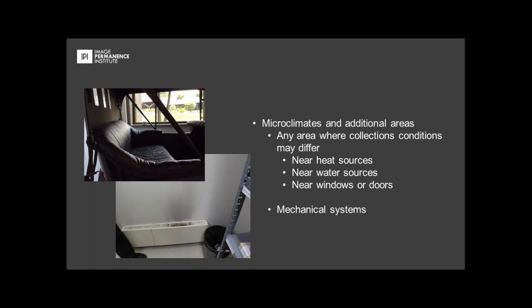In the lower photo, you see a radiator, which is obviously going to be adding heat and drying materials out, especially those stored on the shelf closest to it. Being able to tell how much heat that radiator is adding to the space lets you argue for a lower set point in that area, if possible, among other things.